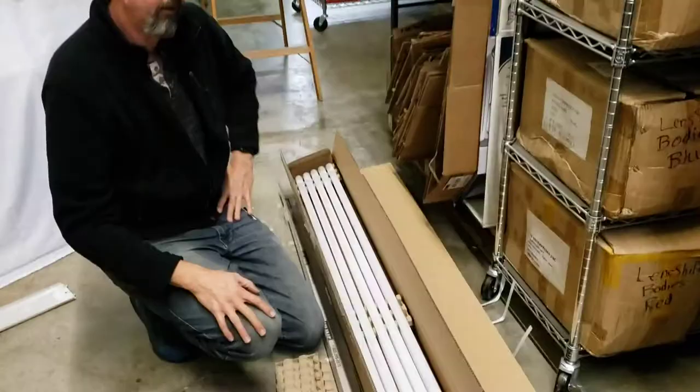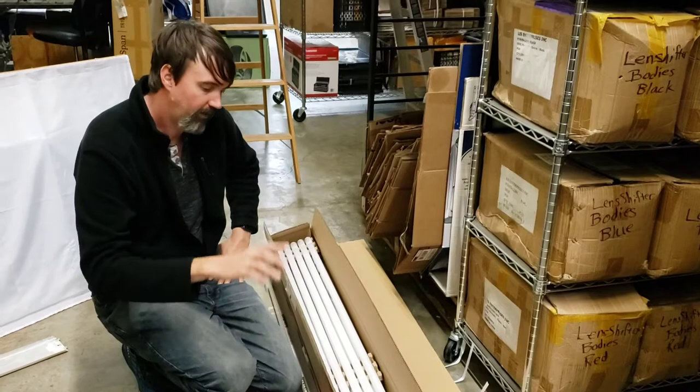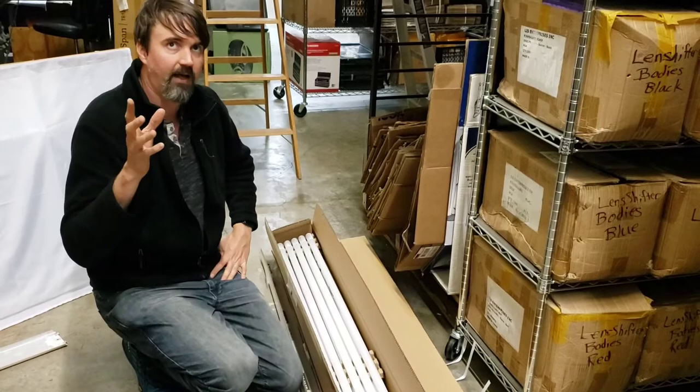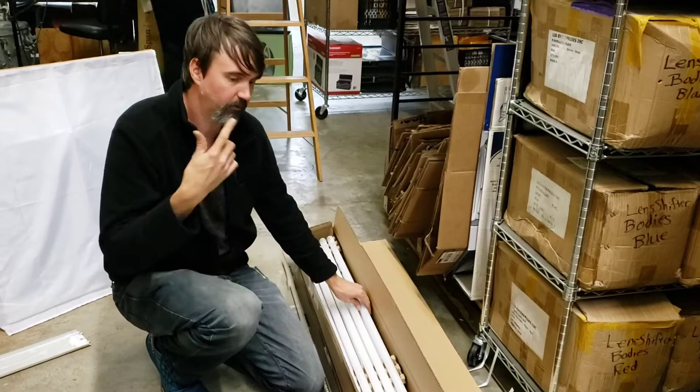There's two different types of these LED bulbs: ones which you can use with your original ballast that are the easiest to install, and ones that are ballast bypass. I chose ballast bypass because if the ballasts are bad, then I would have to replace the ballast. This makes it more future-proof because we can easily replace the bulb and not have to worry about replacing ballasts in the future.